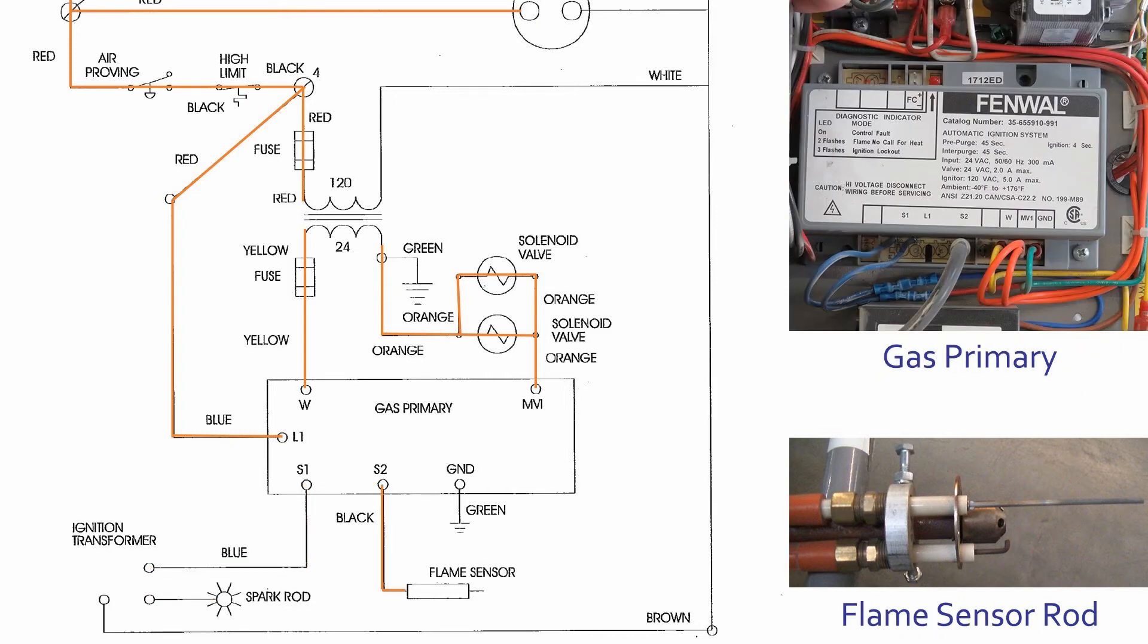The flame rod sensor constantly monitors the flame. If for some reason the burner flame is extinguished, the flame sensor will tell the primary control to stop the fuel flow.